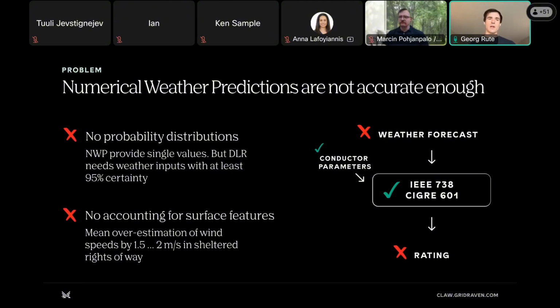Then they don't account for surface features. Numerical weather predictions at best take 1 by 1 kilometer resolution mean features, so-called surface roughness. As a result, because they don't account for individual trees, they overestimate wind speeds by up to 2 meters per second in sheltered rights of way. That overestimation is a safety risk if the weather prediction is used in the rating directly.